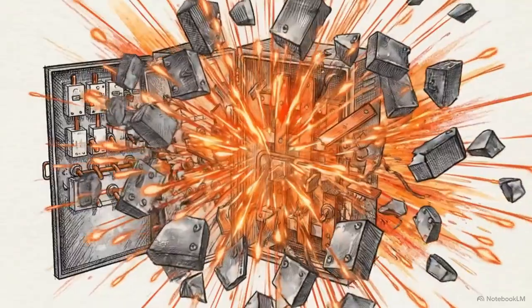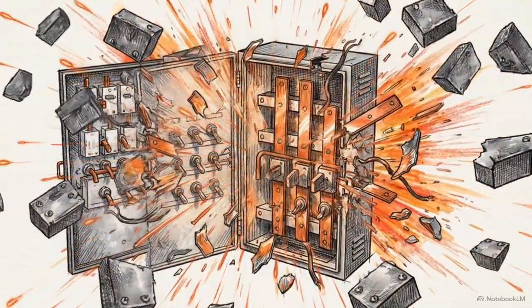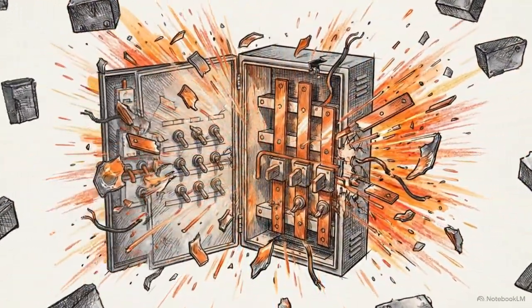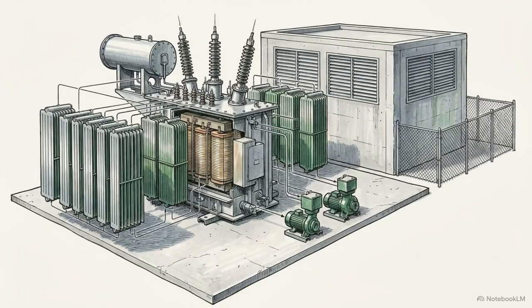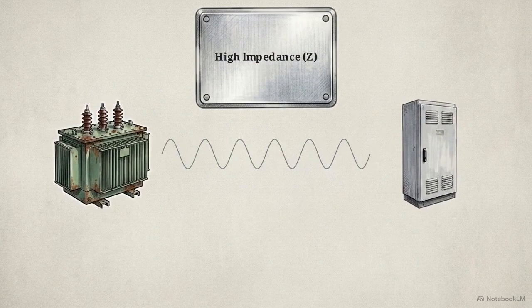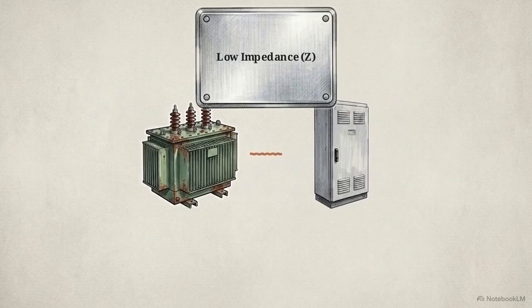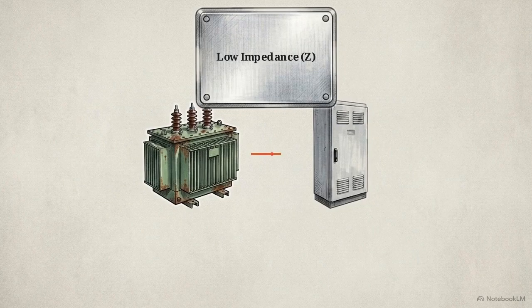As commercial electricity consumption scales up, facilities require massive supply transformers. To handle the load efficiently, engineers are placing these high-capacity transformers closer to main switch rooms. This physical proximity removes the natural resistance of long cable runs. It drastically increases the prospective fault current, or PFC, that can surge into an installation node during a dead short.